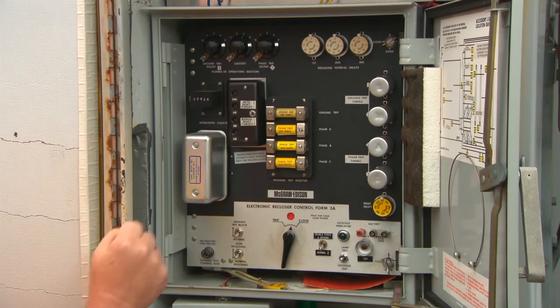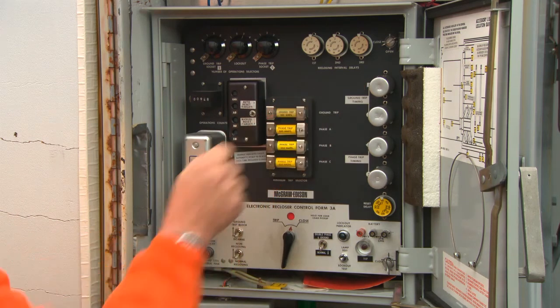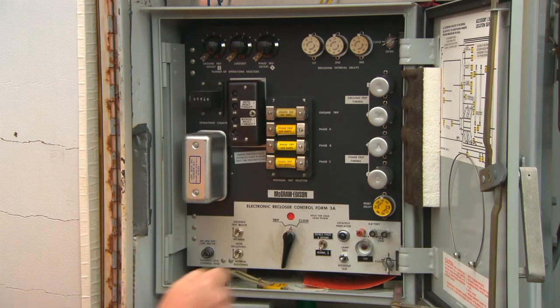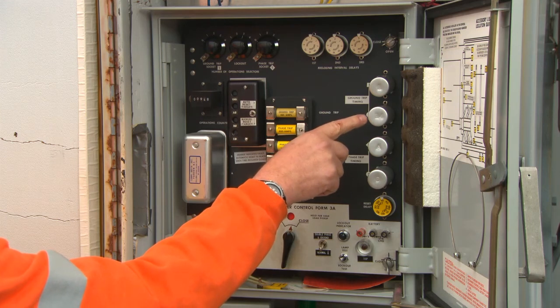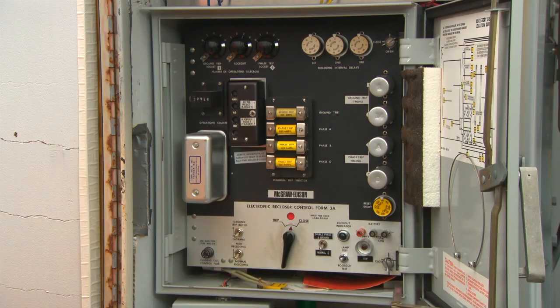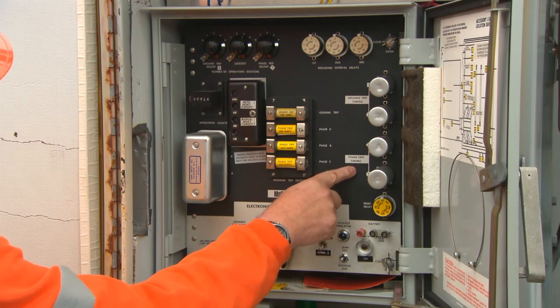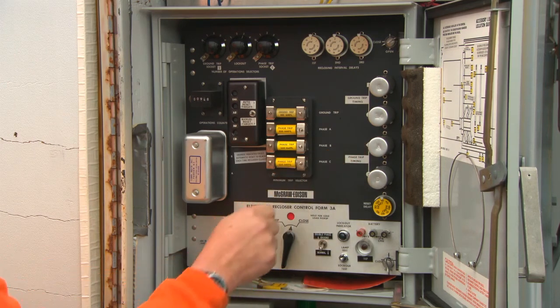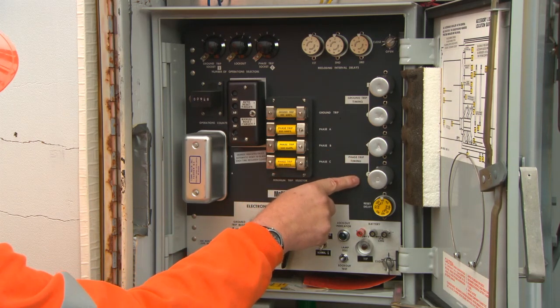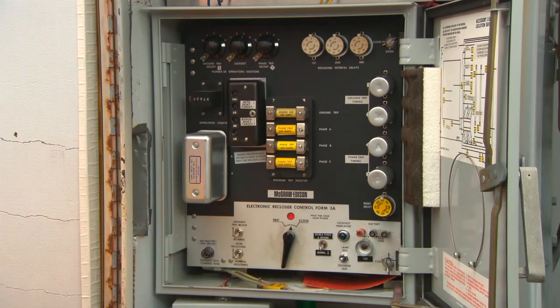For the first ground trip socket, this is your fast curve, a number 1 trip coil curve. The second socket is for the slow curve, and the plug is a number 14. For the phase trip timing, the third or fast plug is an A for the number 1 curve, and the fourth silver plug is the slow or number 2 curve, and is a D plug. Across the bottom is an adjustable reset delay. Upon closing the control, you will have 10 seconds before the control will revert back to its first operation.